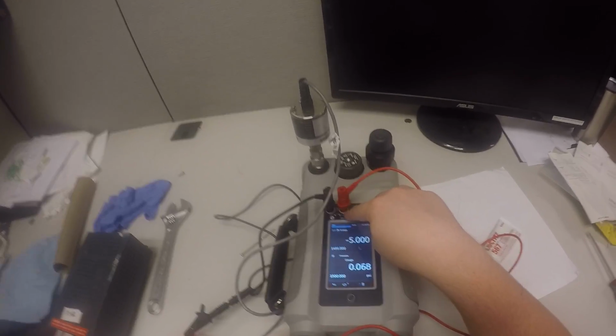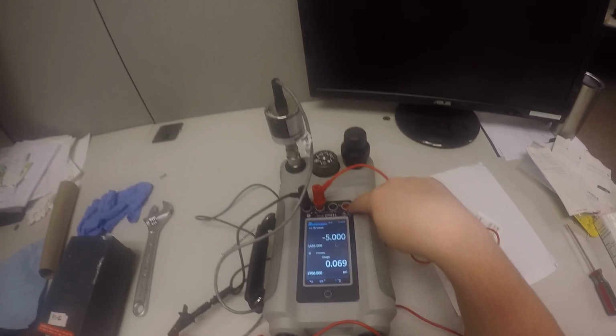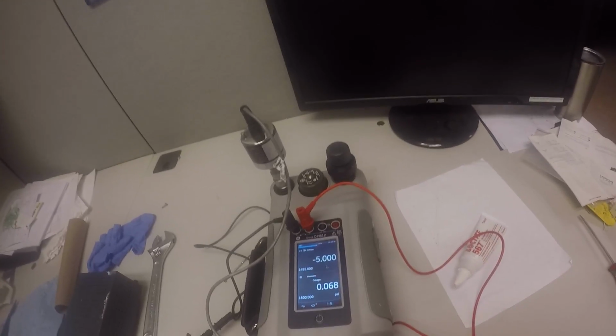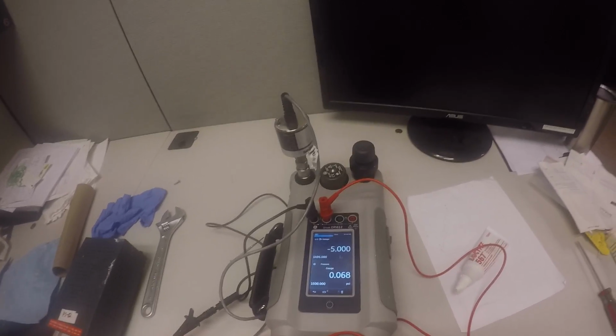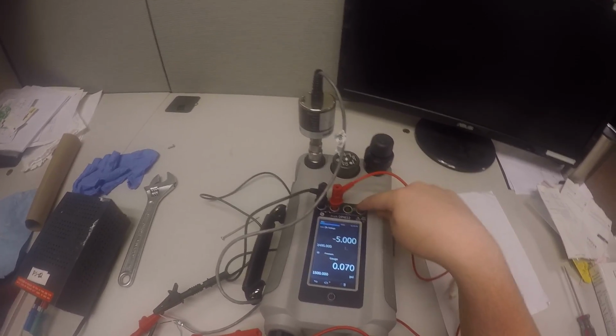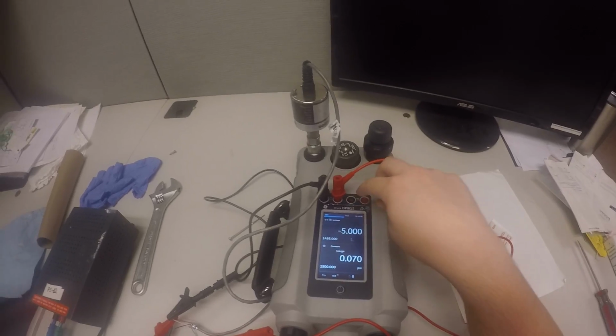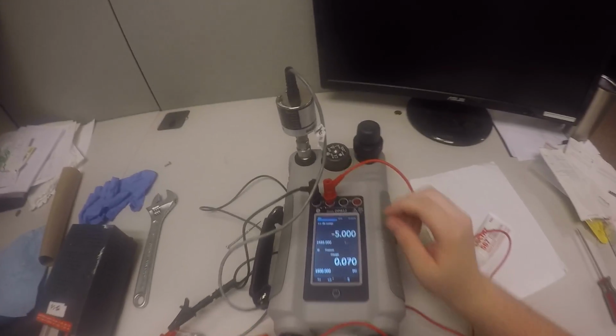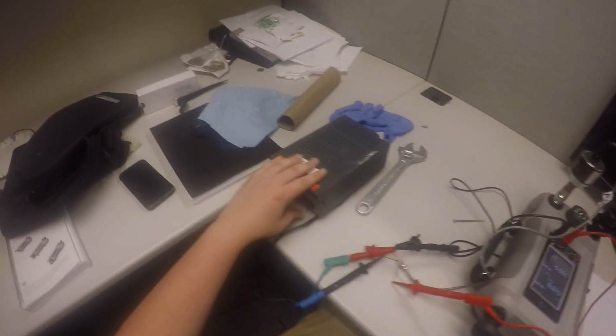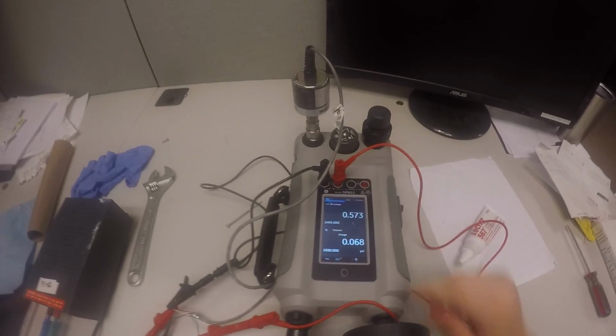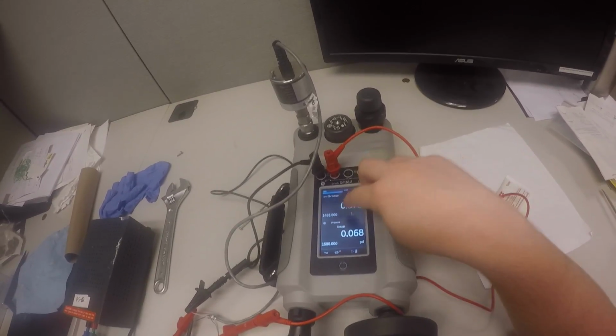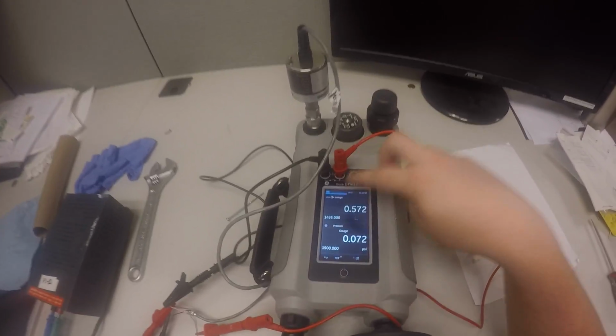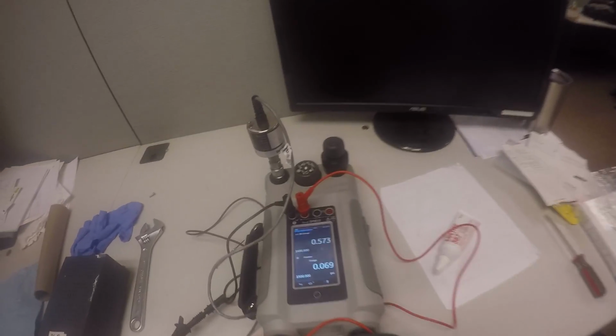And as you notice on the Druck, the left side is for inputting into the Druck, and the right side is for output out of the Druck. So if the transducer has under 10 volts, you can use these two ports right here to extract your voltage. Alright, and we're pretty much ready for the test, so we're going to turn on our power supply. Now you see that the top section jumped from -5 to 0.5, and that's in PSI right now. So now it's having a measured voltage, so we know we correctly did that.